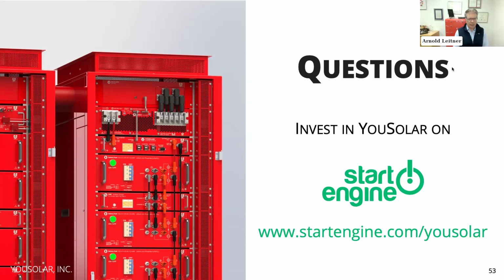On UL certification: we certify everything to UL, and I believe we've passed every UL certification we've attempted without having to go back and redesign anything. We believe we design well above UL safety standards. All the batteries currently being installed are in process for UL 9540A certification, and then we do the whole system UL certification, which can cover different configurations. So yes, you can build any system configuration you want, and there is a UL certification that covers that combination - that's the one we're pursuing, or in progress on, I should say.